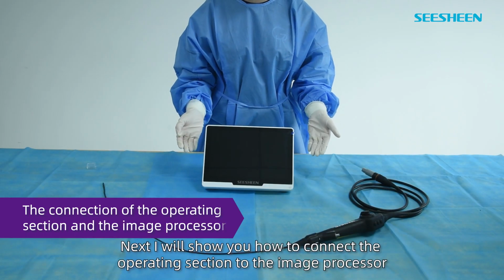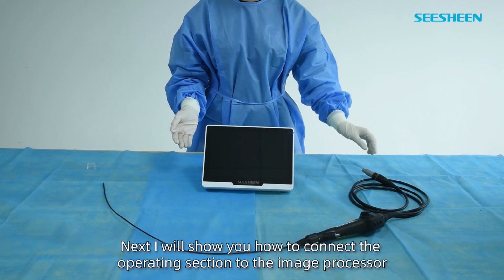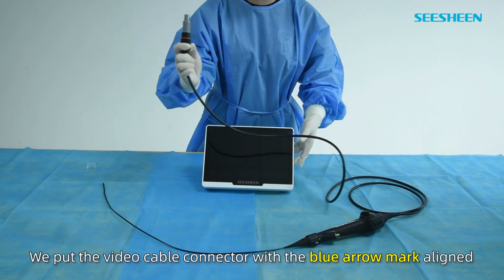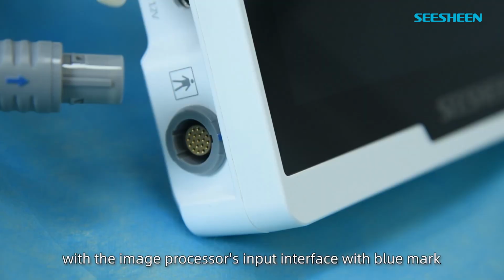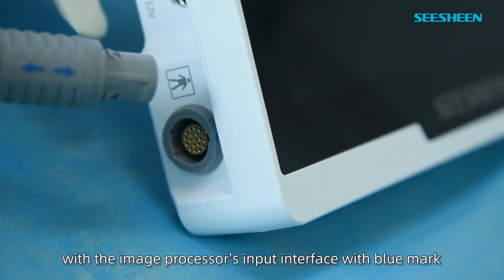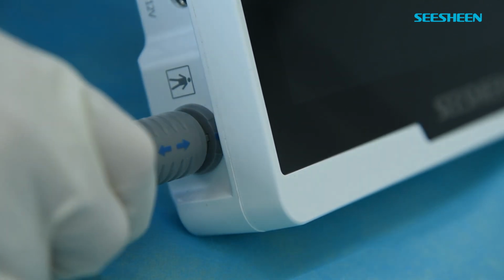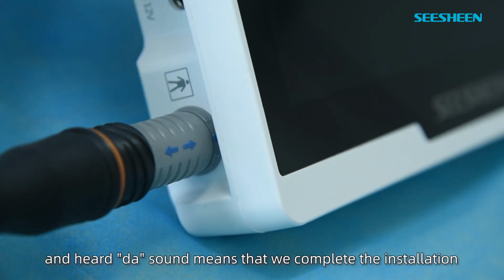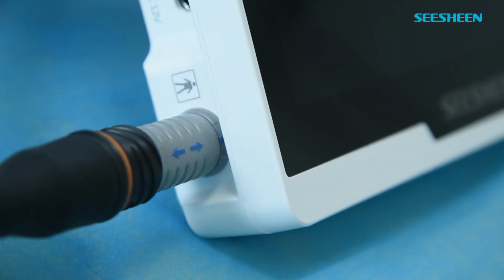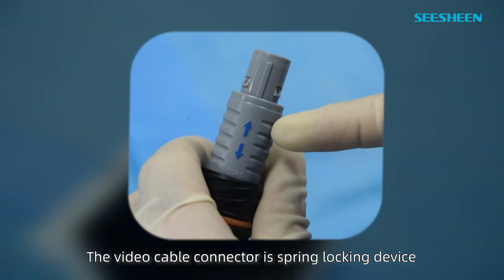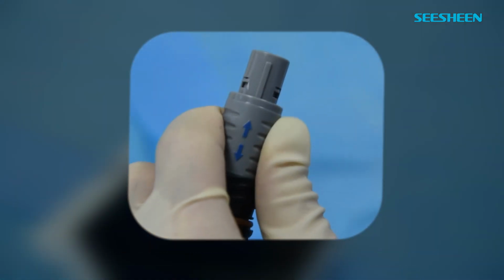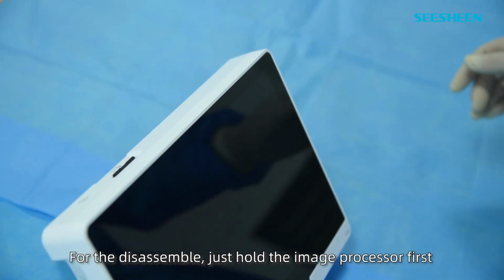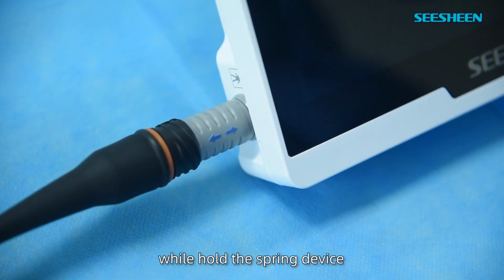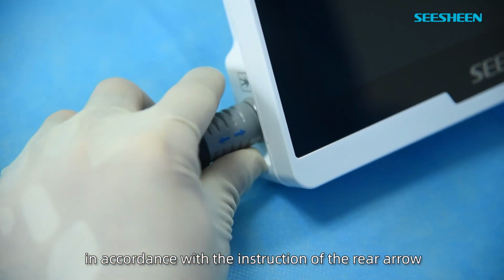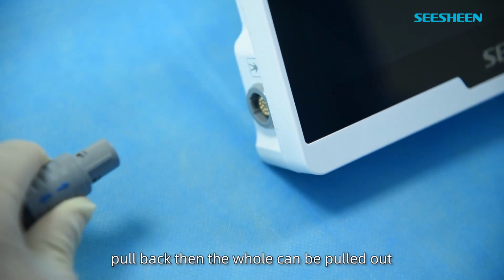Next I will show you how to connect the operating section to the image processor. We put the video cable connector with the blue arrow mark aligned with the image processor's input interface with blue mark. Insert it and press, and the click sound means that we complete the installation. The video cable connector is a spring locking device. For the disassembly, just hold the image processor first. While holding the spring device, in accordance with the instruction of the rear arrow, pull back, then the connector can be pulled out.